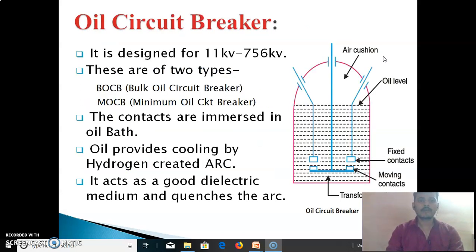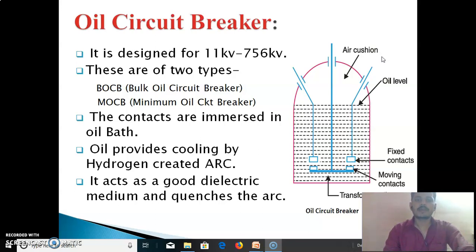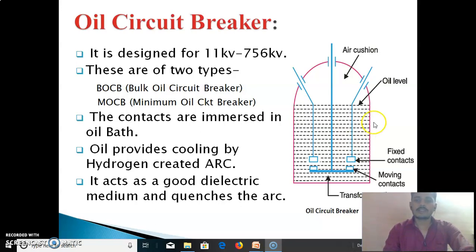First, we see the oil circuit breaker. When the fixed contact and moving contact are placed in oil, they are known as an oil circuit breaker. It is designed for 11 kV to 756 kV. There are two types: bulk oil circuit breaker, where the oil level is maximum, and minimum oil circuit breaker, where the oil level is minimum. The contacts are immersed in the oil bath. Oil provides cooling by the hydrogen created arc, acts as a good dielectric medium, and quenches the arc. In the diagram we can see the fixed contact, moving contact, transformer oil, oil level, and air cushion.